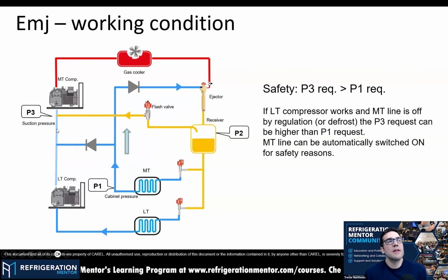So that would mean, if you get a really low load condition, all the curtains are pulled down, all the low temp cases are satisfied. A lot of people worry about high temperature outside, hot days. But I've seen more people, especially in our CO2 training programs, where a lot of issues happen when it's super cold out. They don't think about that because everything satisfies and shuts off, and that's not good for a system, especially a booster system. You need something to run. So for this example, the ejector will send some more discharge gas through the flash gas valve to keep the suction pressure up on the medium temp. Is that correct?